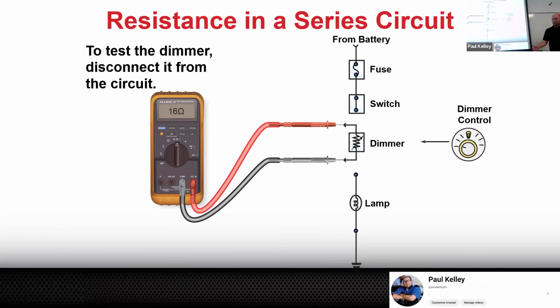So sometimes just to really be sure that I'm not tripping, I'll measure available voltage and think, that's wrong. I'll voltage drop it, that's wrong. I'll measure resistance, that's wrong. I know it's wrong. I can prove it's wrong in 3 different ways, you know. And sometimes I don't do that because it's kind of redundant.